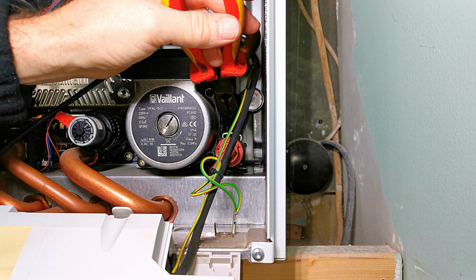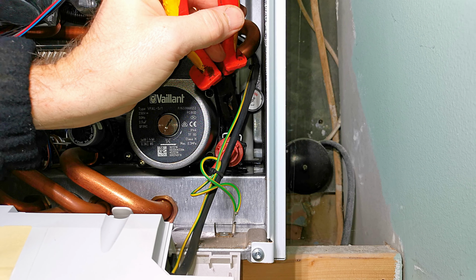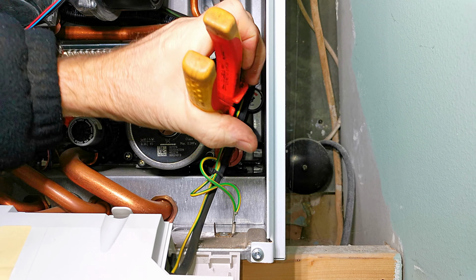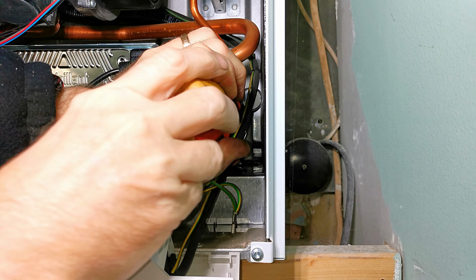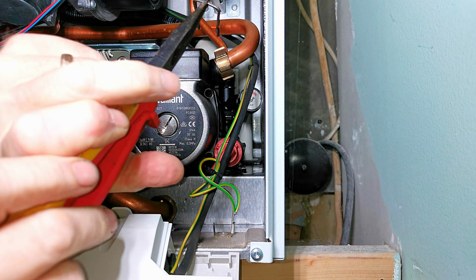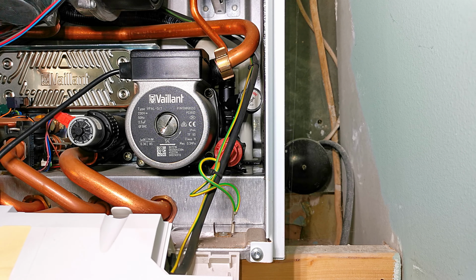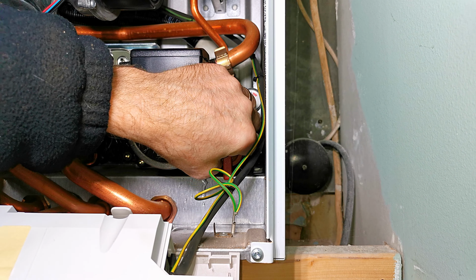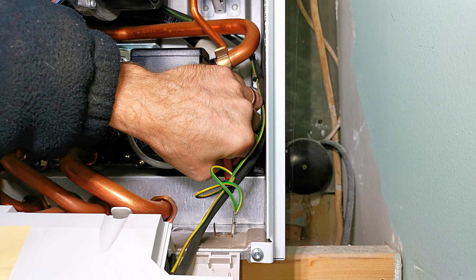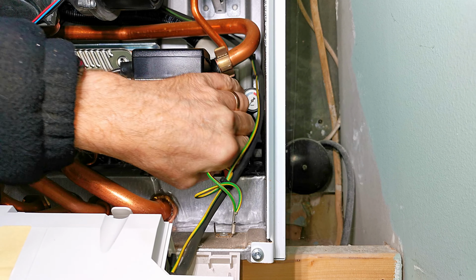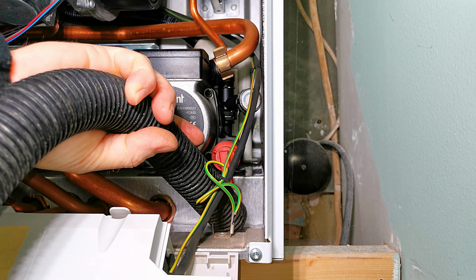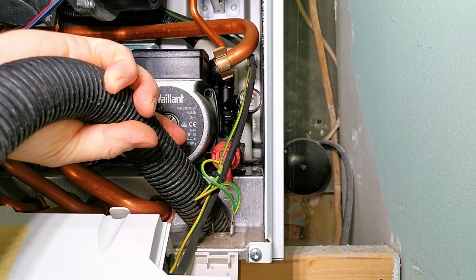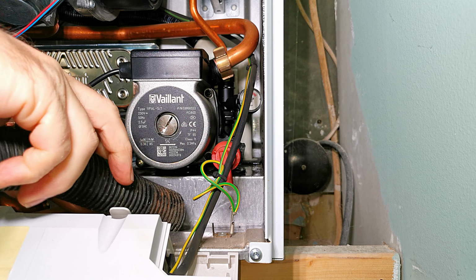I'm now going to remove the pressure relief valve, and there's a little retaining clip again, so I just use my long nose pliers, pull that clip up to release the valve. And there we go, there's the clip. And now give the valve a wiggle and pull it forward to release it from the pump body. As soon as it releases from the pump body, I'm going to get more water come rushing out to the lower part of the boiler. But I just suck that up again with my water vacuum.